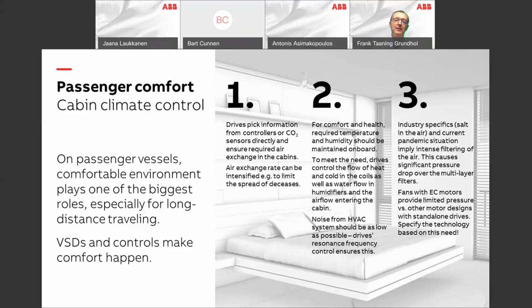While doing that, the other aspect, which is often forgotten, is actually noise. One of the things that annoys me the most is when I come into a room and there's a fan running somewhere that sends noise through the ductwork, and I can hear that constant humming of the fan. By applying variable speed, you can reduce the speed of the fan, and the speed and noise ratio is a logarithmic function. So by a small reduction in speed, you get a significant reduction in the perceived acoustic pressure from the fan.